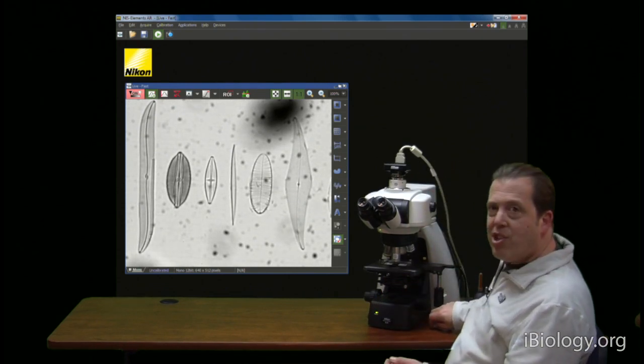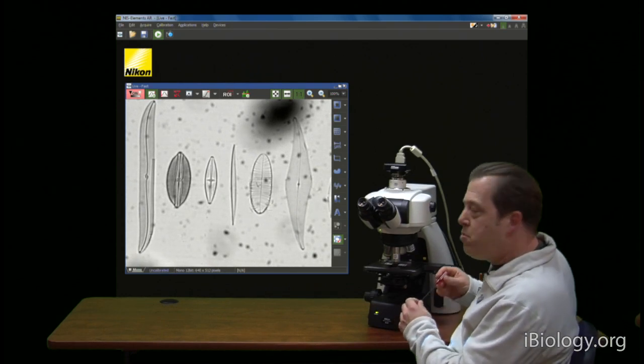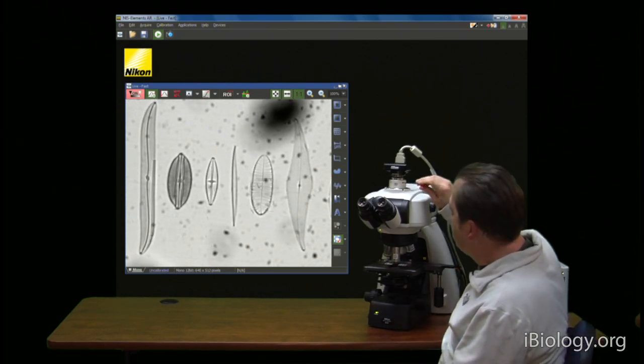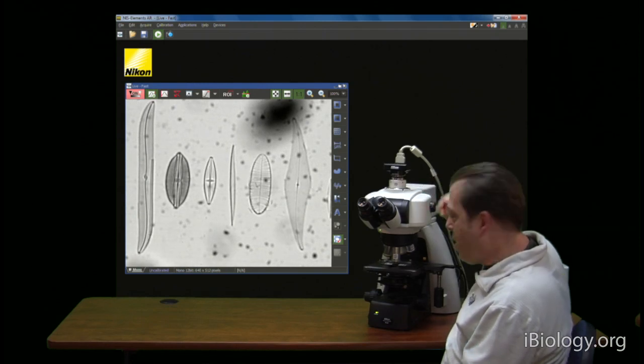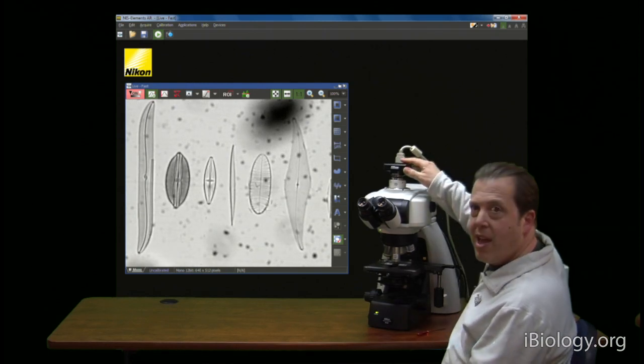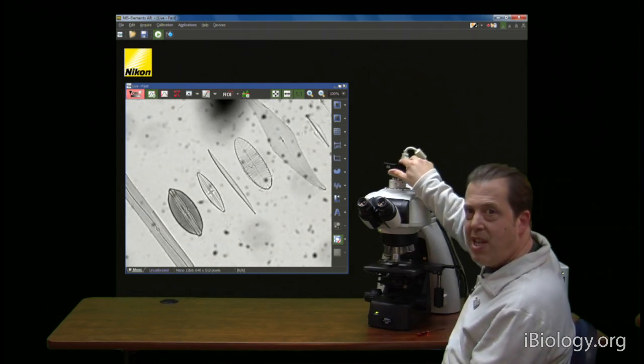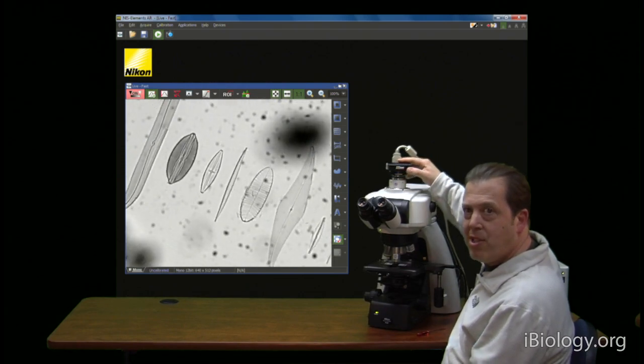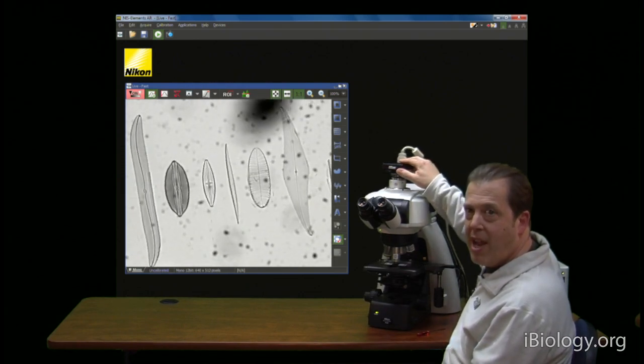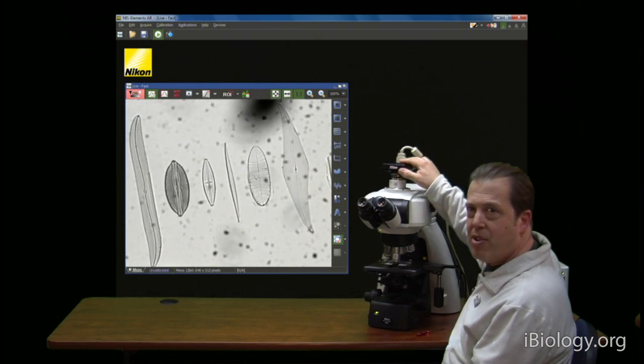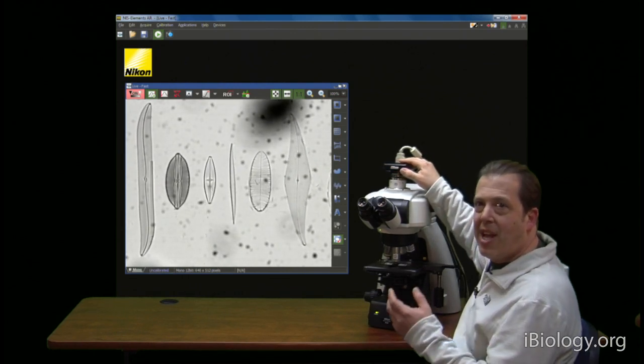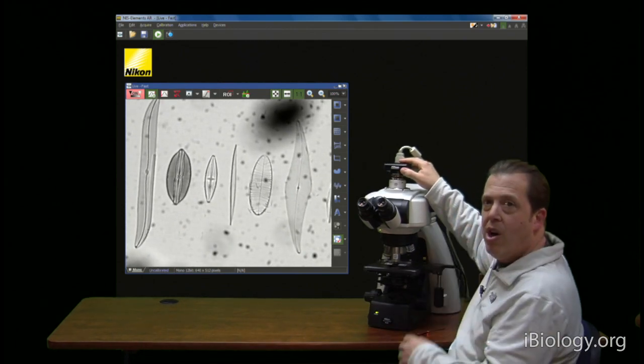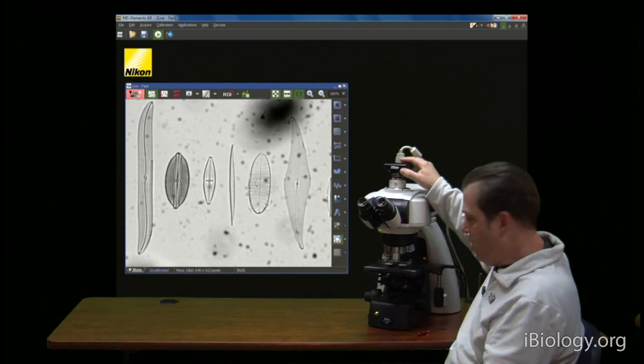So the way we check and see if the dirt is on the camera is by actually rotating the camera. So let's loosen up the camera in the C-mount and rotate that. And what you can see is some dirt and the specimen is rotating relative to the camera when I turn the camera, but there's a lot of dirt that is actually not moving. And that means it's actually on the window or the camera detector.